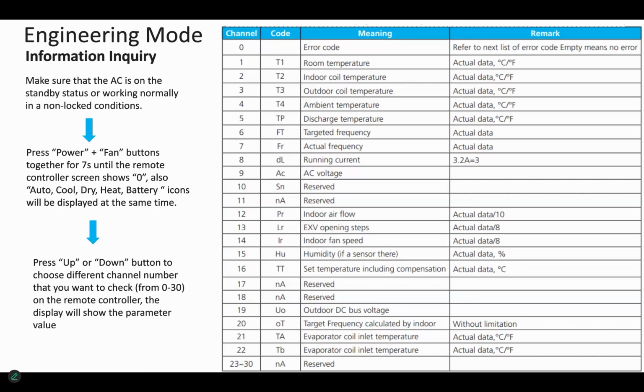TT is set temperature after compensation. That is if somebody was to set temperature compensation on this machine to compensate for a difference in height. So let's say it was using T1, the actual T1, instead of the room temperature. On the wired wall control, you can actually change the compensation and make it read more like what the room temperature is, and that actually helps with comfort control. It works the same as ductless temperature compensation does, where you're trying to compensate for stratified air layers.